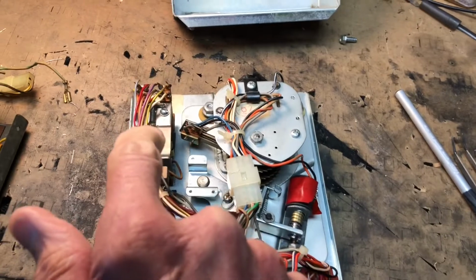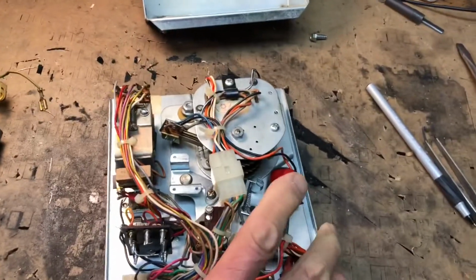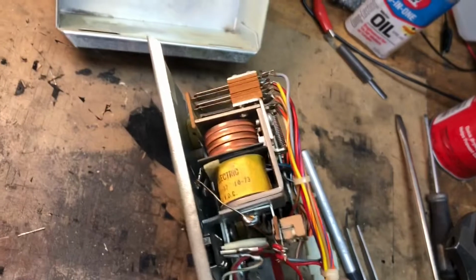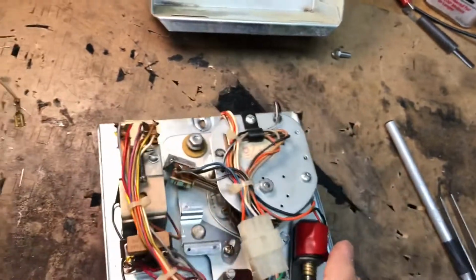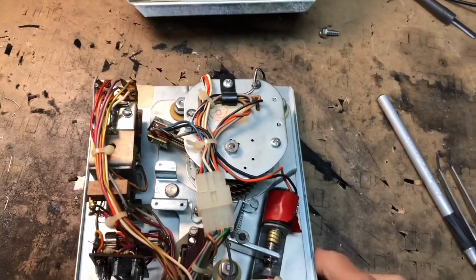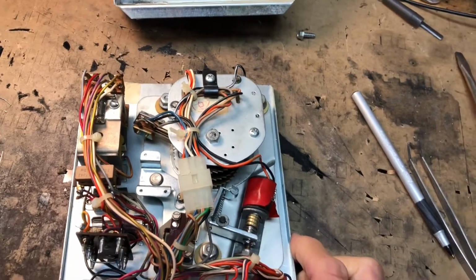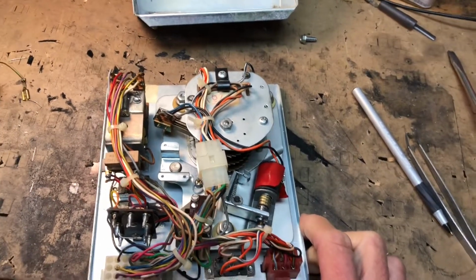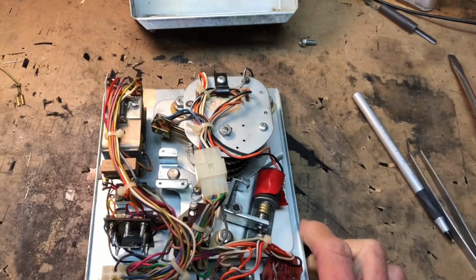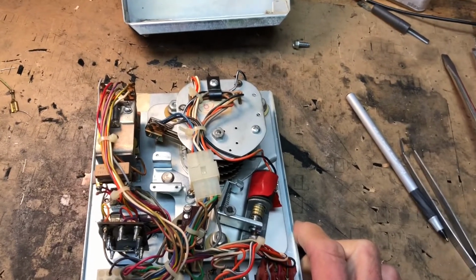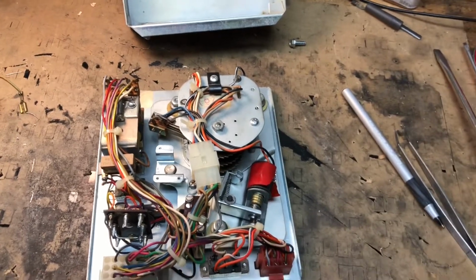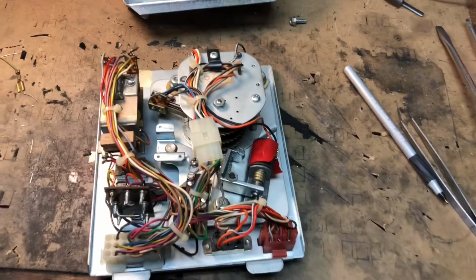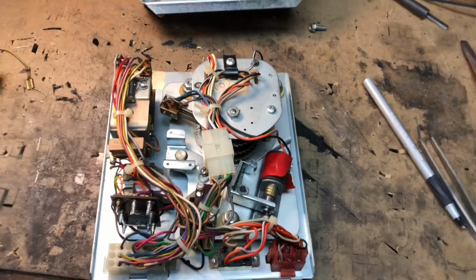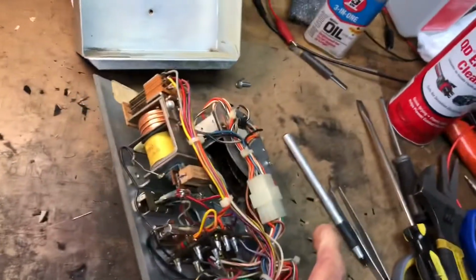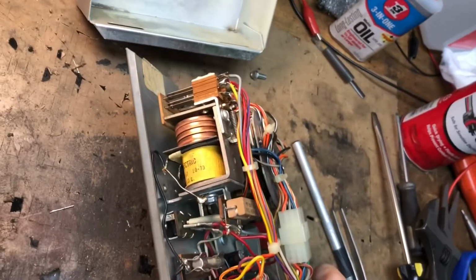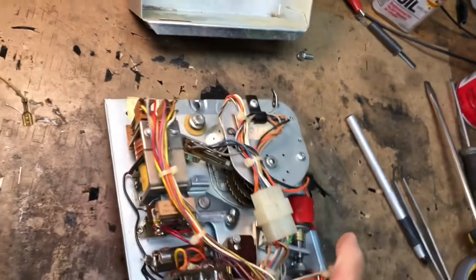This is the ADR relay here. Now, this is very important. There are 4 contacts there, and I must say those must be cleaned thoroughly, because even if the relay is not actuated, if it's in the rest position or closed position, those contacts still carry current to operate a lot of other functions. So it's a very important relay. 4 sets of contacts, be sure they are cleaned.